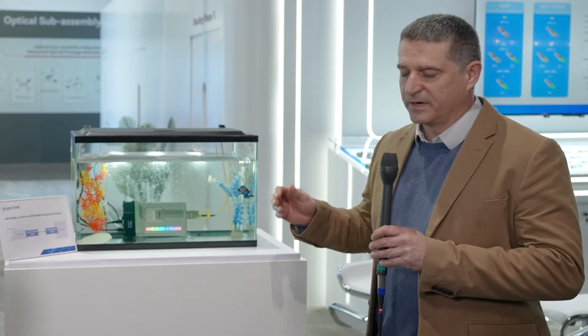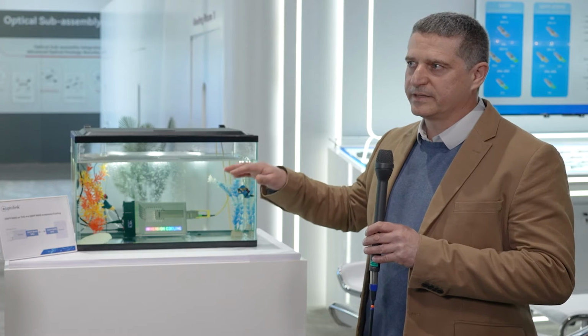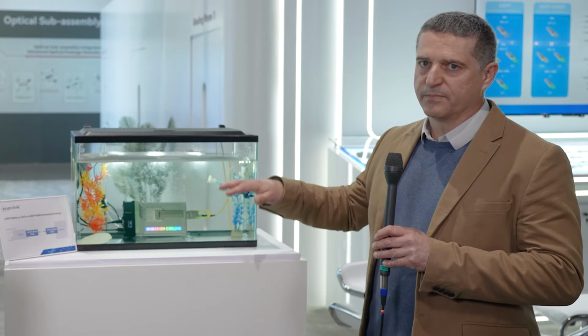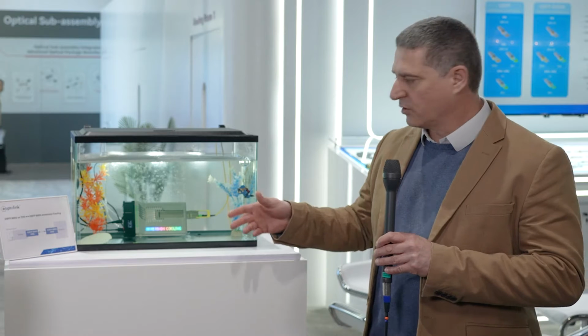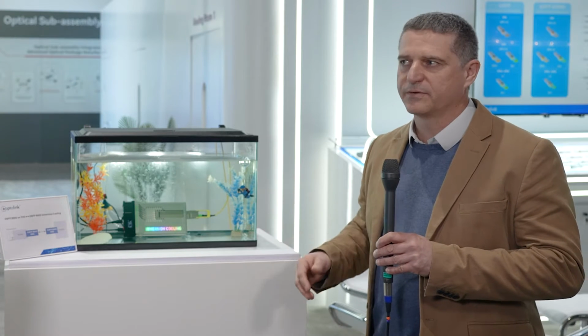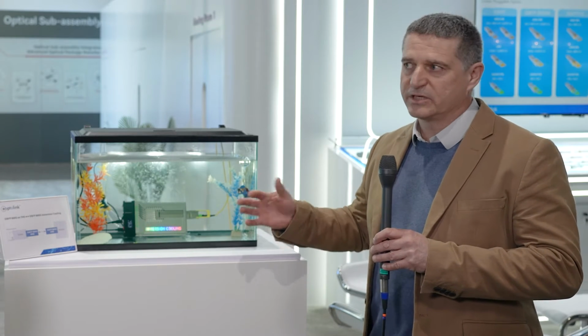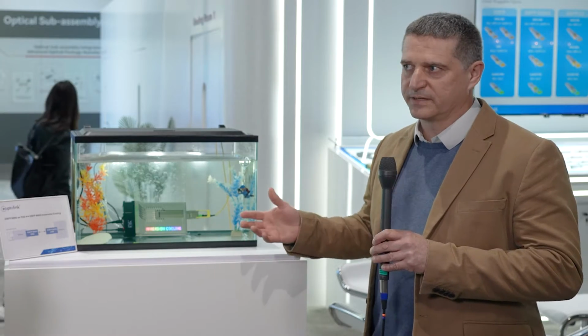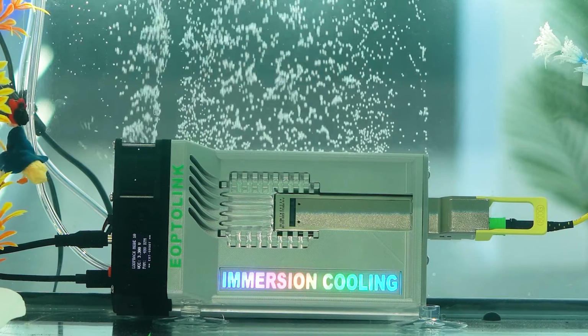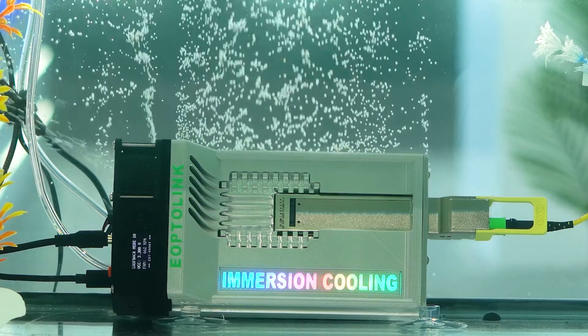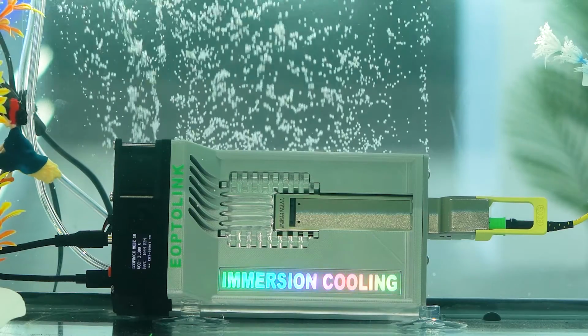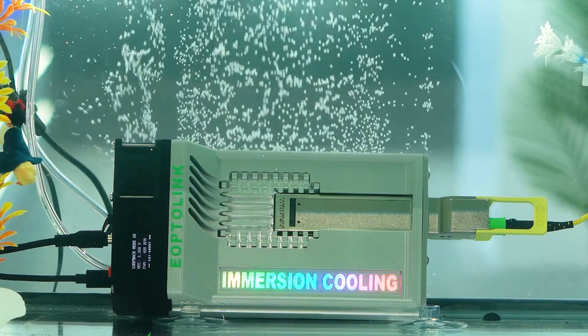From a power consumption perspective, do you have any advantages if you do liquid cooling? Yes, definitely. First, the operating temperature of the module is much lower. This one here is in operative mode now at 37 degrees Celsius, which is much lower than the usual temperature of 60 degrees. One possible advantage could be that the lifetime of the modules could be much longer because of the lower operating temperature.